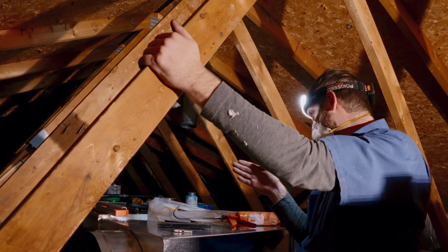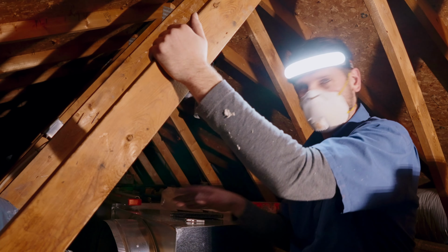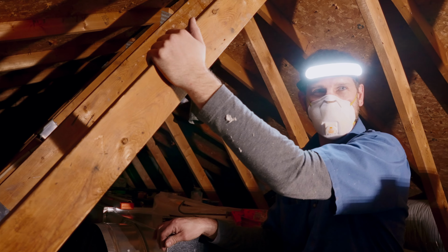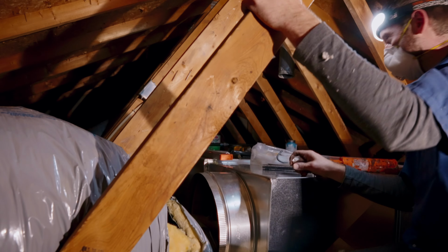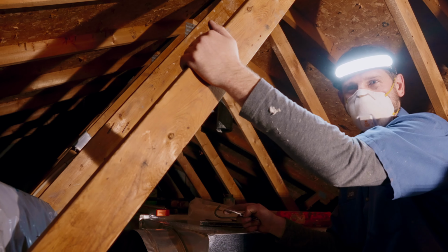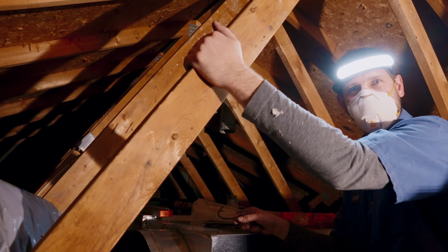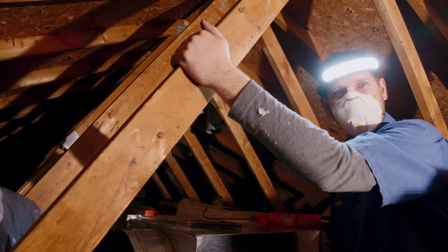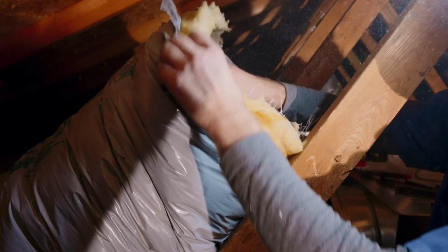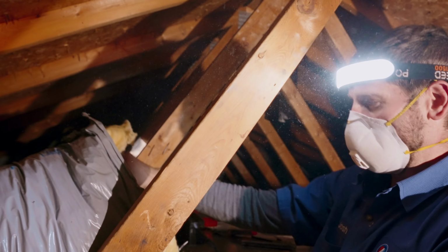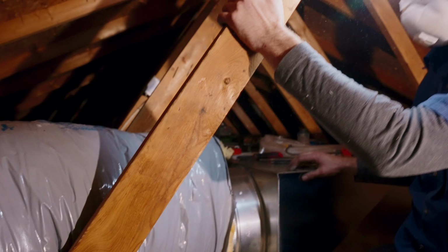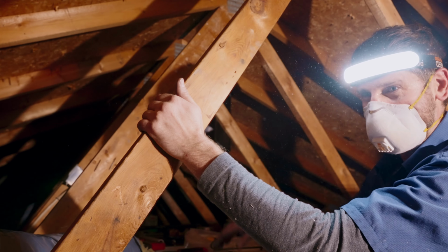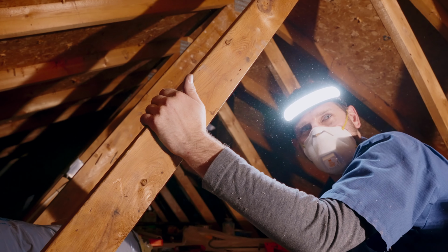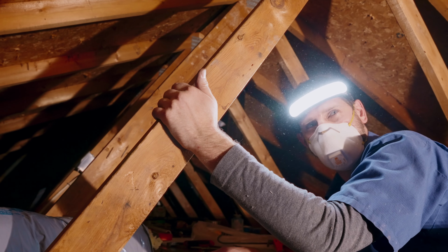And then being up here like it is, not in a basement, you'd risk getting water damage in your ceiling and everything. We got a drain pan with a built-in safety switch. So any little bit of water that it senses, it'll kick the unit off, not let it run, keep generating the condensation. So you can see this 16-inch flex duct. The black part's the actual duct, and then this is insulation. Again, we're in the attic. Our return plenum is also insulated on the inside, as well as the supply. Because in the unconditioned space up here, you gotta have it insulated or you can have condensation issues.